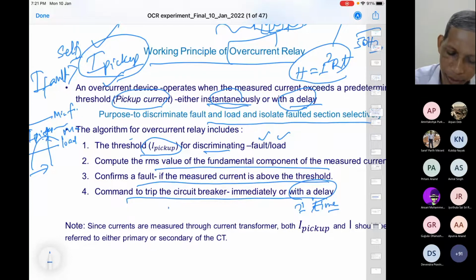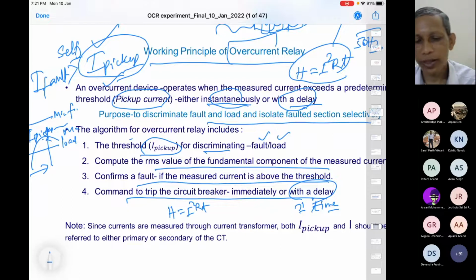Again, the same H equals I squared R T. What you can see here is that I can allow the time to be longer if the fault current level is smaller. If the fault current level is higher, the decision time should be smaller; the trip command time should be smaller. That is the simple logic. However, because of the square term of current, it should be non-linear. And that's where inverse definite minimum time characteristics come in. We'll come to that.